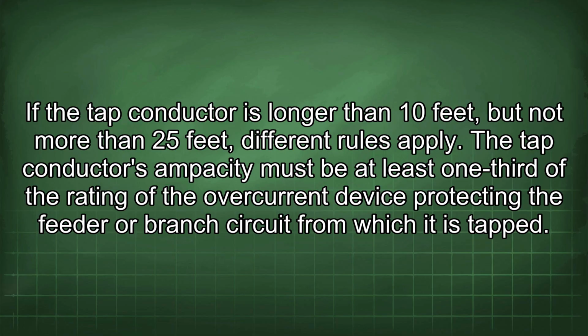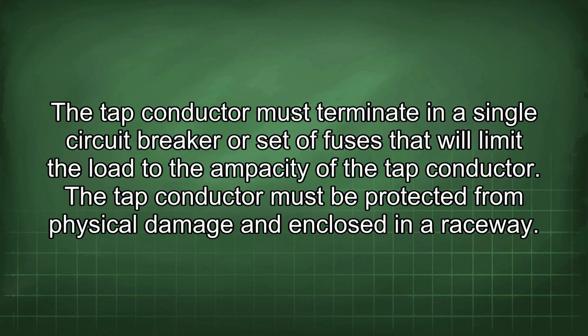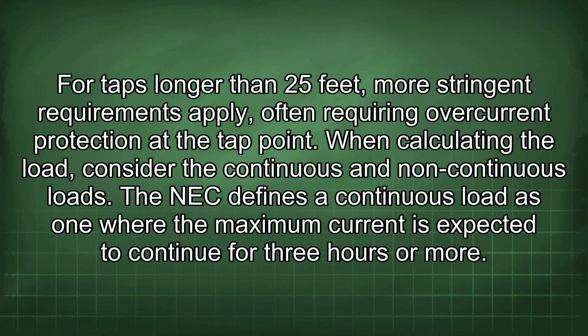If the tap conductor is longer than 10 feet, but not more than 25 feet, different rules apply. The tap conductor's ampacity must be at least 1/3 of the rating of the overcurrent device protecting the feeder or branch circuit from which it is tapped. The tap conductor must terminate in a single circuit breaker or set of fuses that will limit the load to the ampacity of the tap conductor. The tap conductor must be protected from physical damage and enclosed in a raceway. For taps longer than 25 feet, more stringent requirements apply, often requiring overcurrent protection at the tap point.